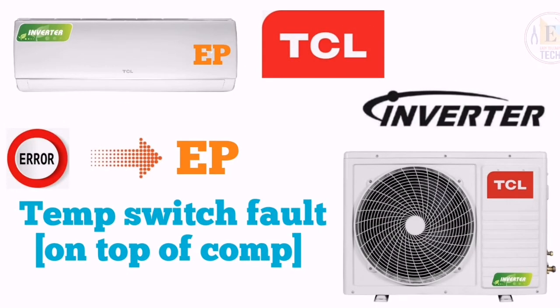When you see error EP, it means temperature switch fault, which is installed on the top of our compressor. First of all, you have to check the CN3 of the compressor top temperature wire switch on the outdoor power board. If it is loose, connect it properly, and if it is connected properly, then you have to check the compressor temperature.